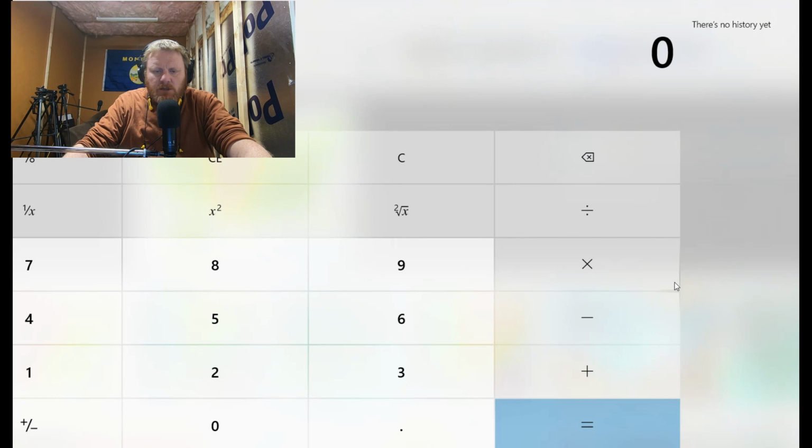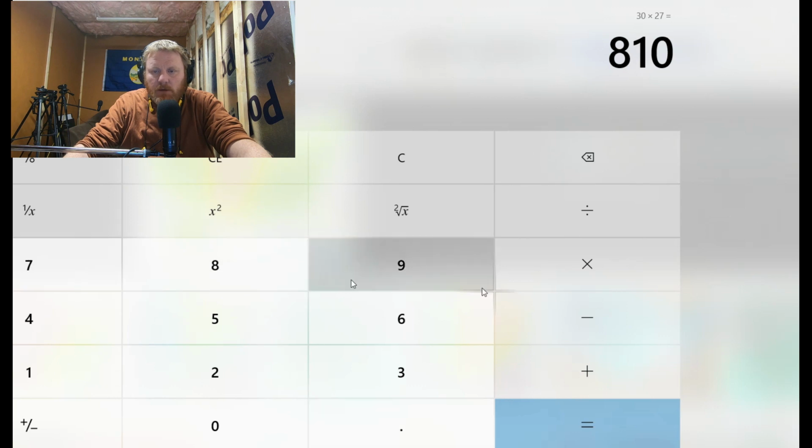So I can run my generator for 3 hours. I'm generating 30 amps. I have an amp gauge, and I run 30 amps. That's the maximum that the wire will handle, and I don't want to overheat my alternator either. So I can times that by the voltage that I'm putting out, which is around 27 volts on average. So I get a number of about 810 watts, all right? And in an hour, I can make 0.81 kilowatts.